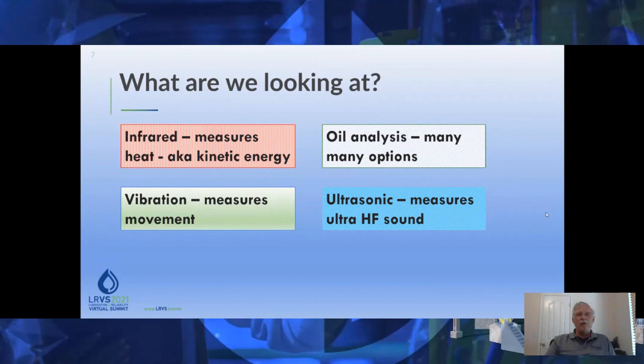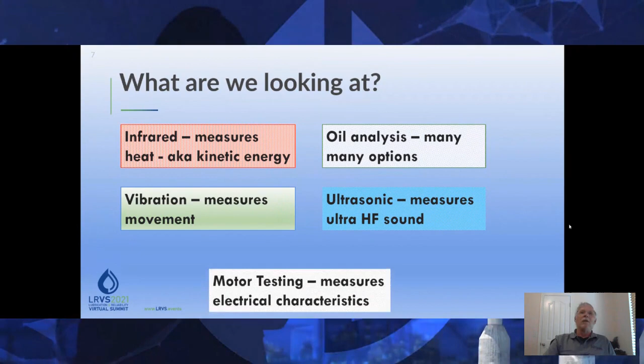Ultrasonic surveys are measuring ultra high frequency sound, but again, you're measuring the energy that is created by that noise. And motor testing, again, there's a number of things, but typically when you're doing motor testing, you're either checking for the condition of the insulation, or you're checking to see if the electrical characteristics of the motor are what they should be. Again, you can think about this as energy, right? The insulation resistance is to keep the energy in. The electrical characteristics are to make sure that the energy is doing the right things for you.